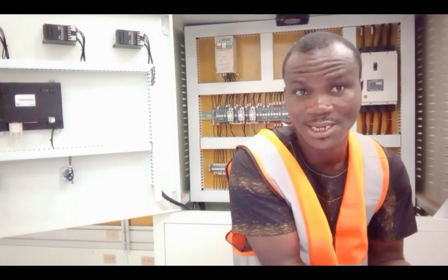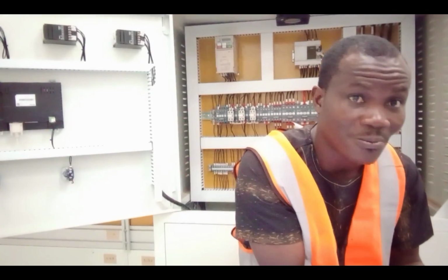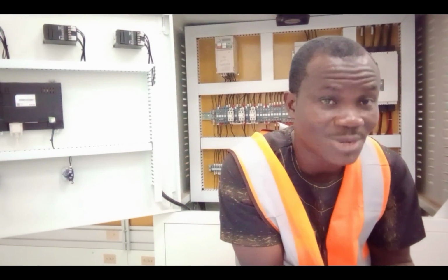In the case of the RCCB, it is not like that. If you want to use an RCCB in a lighting circuit that is protected with 6 amp breaker, you add the RCCB to the MCB that is already there. So you are using both the RCCB and the 6 amp miniature circuit breaker, so that the miniature circuit breaker will protect the circuit from short circuit and overload, whilst the RCCB is protecting the circuit from leakage and is protecting the users from electric shock.